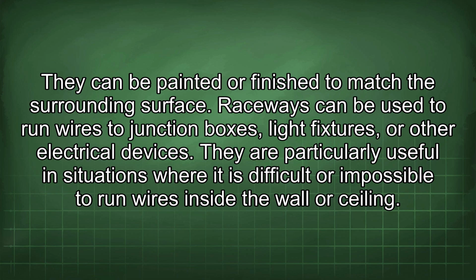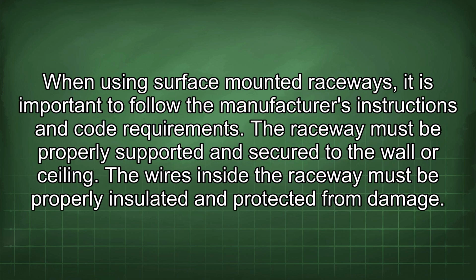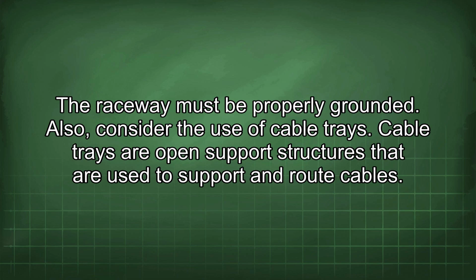Raceways can be used to run wires to junction boxes, light fixtures, or other electrical devices. They are particularly useful in situations where it is difficult or impossible to run wires inside the wall or ceiling. When using surface-mounted raceways, it is important to follow the manufacturer's instructions and code requirements. The raceway must be properly supported and secured to the wall or ceiling. The wires inside the raceway must be properly insulated and protected from damage. The raceway must be properly grounded.